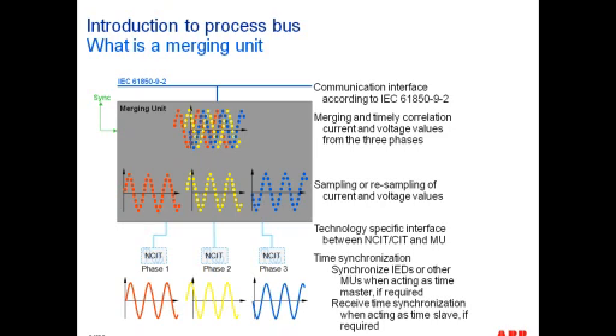And the merging unit essentially is going to have an Ethernet port that it would use to publish these individual current and voltage samples. And we will see later on in the presentation what one of those Ethernet frames looks like. But in essence, the merging unit is sampling the individual current and voltage signals, and each one of those samples is used to form an Ethernet frame which contains these samples. They're published, and then the protection relays are able to subscribe to that message and use those samples to run their protection functions.